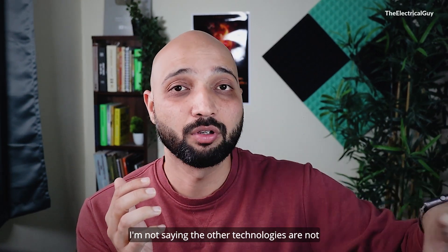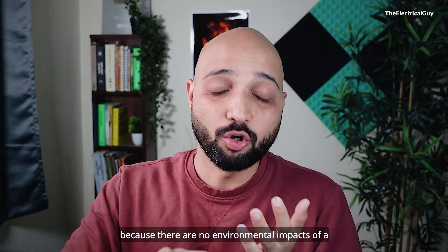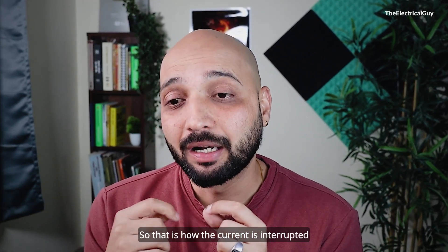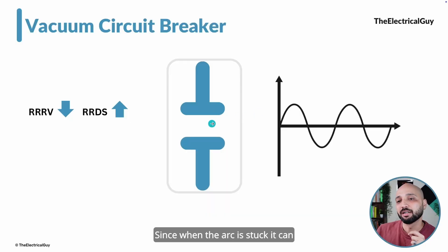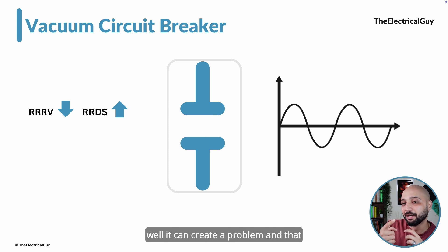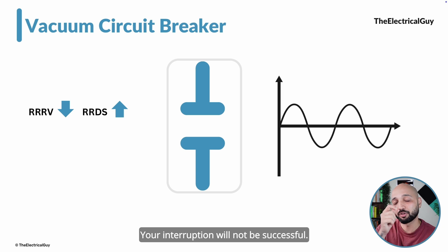Vacuum will score more than other technologies because there are no environmental impacts of a vacuum circuit breaker compared to SF6 technology. That is how the current is interrupted and how the arc is extinguished. There is one issue though: when the arc is stuck, it can heat up the contacts inside the vacuum interrupter. When they heat up, it can create a problem critical enough to reignite the arc, making the interruption unsuccessful.